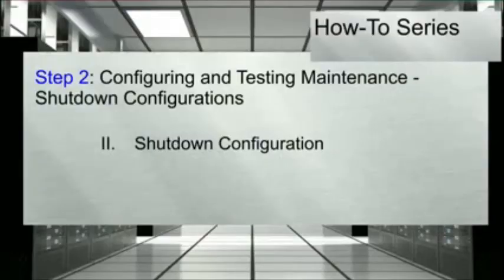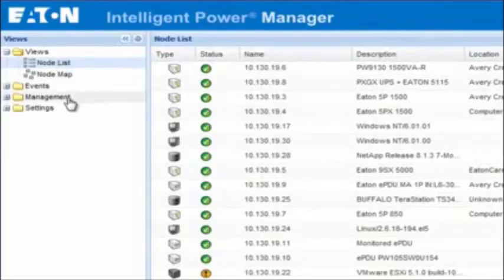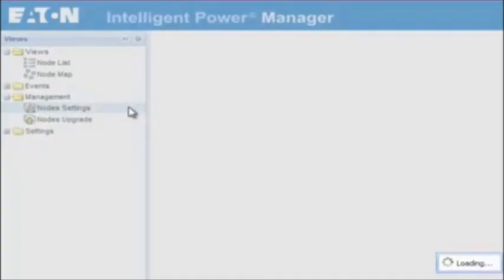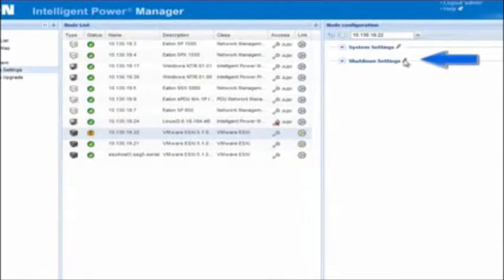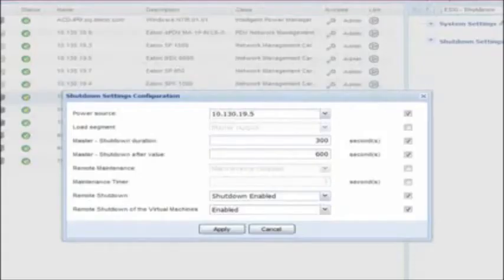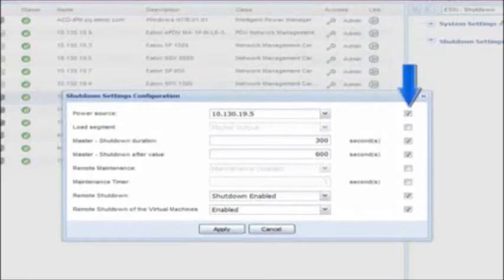Shutdown Configuration. Next, we will review the shutdown configuration. Once the UPS supporting the selected ESXi host experiences a power event, IPM will trigger the shutdown of the designated host. In order to set the parameters, start from the IPM view screen. Select the folder titled Management and click on the option for Node Settings. Choose the VMware ESXi host that you would like to configure. Once selected, the Node Configuration pane will open to the far right of the screen. Click on the pencil icon beside the option titled Shutdown Settings. The Shutdown Settings configuration text box will appear. The parameters selected will enable IPM to take action with the designated escalation mode.